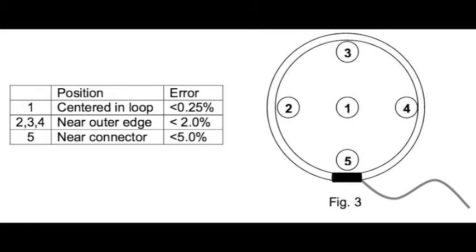Let me stop here to show a diagram of a traditional Rogowski coil. Note that the closer to the center the primary conductor is located, the smaller the error. Of particular interest, the error in position 5, which is near the connector, shows the greatest amount of error. This is how the teardrop Rogowski coil reduces error by avoiding getting close to the connector. You'll see this in the installation.